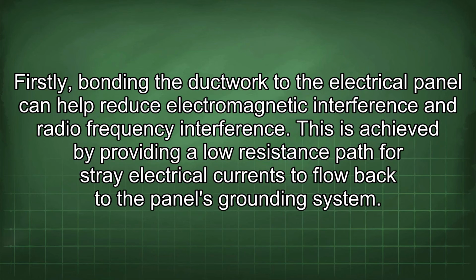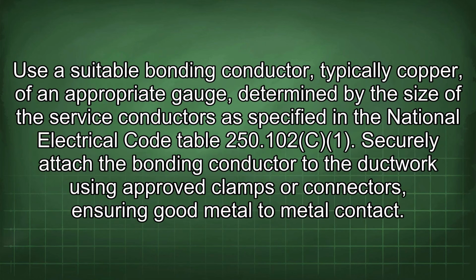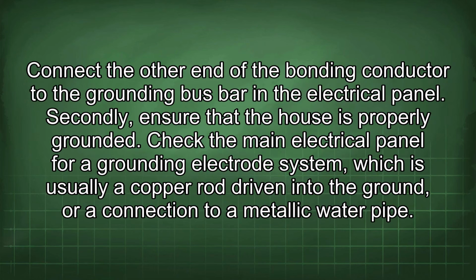This is achieved by providing a low resistance path for stray electrical currents to flow back to the panel's grounding system. Use a suitable bonding conductor, typically copper, of an appropriate gauge determined by the size of the service conductors as specified in the National Electrical Code Table 250.102. Securely attach the bonding conductor to the ductwork using approved clamps or connectors, ensuring good metal-to-metal contact. Connect the other end of the bonding conductor to the grounding bus bar in the electrical panel.